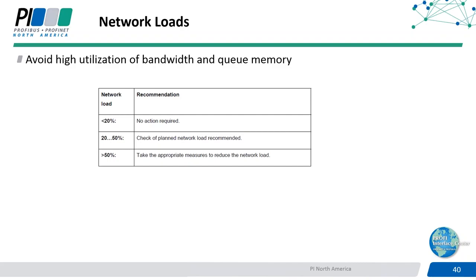So PI recommends that the network load on PROFINET systems be between 0 to 20% on your critical points for ideal conditions. If you're above 20% on a section, then you're probably going to need to look at some of the topics we're talking about next, which will be your I/O cycles and your network layout. You might need to add or change some components. Maybe you're overloading some parts of your system, and check those things per the design guideline that we have.